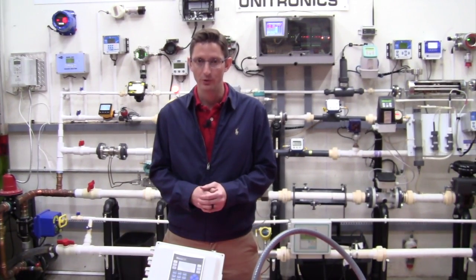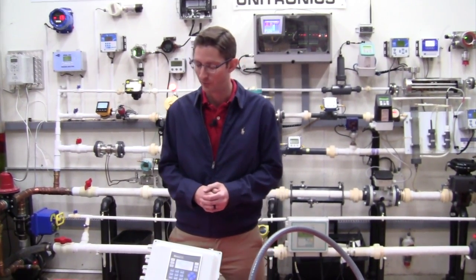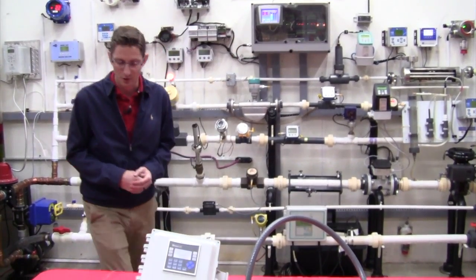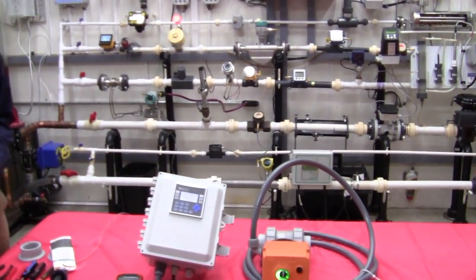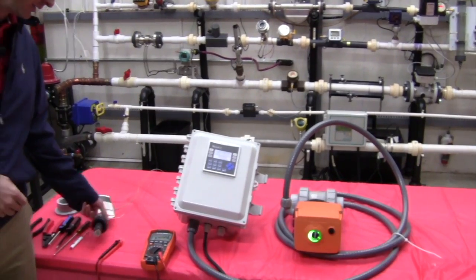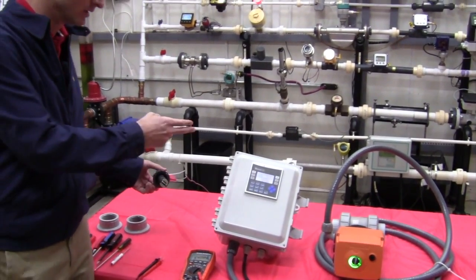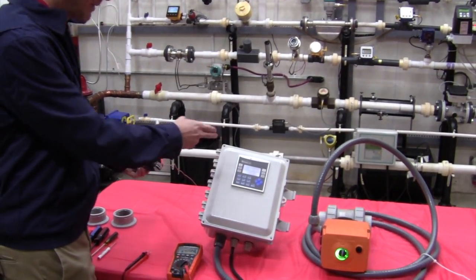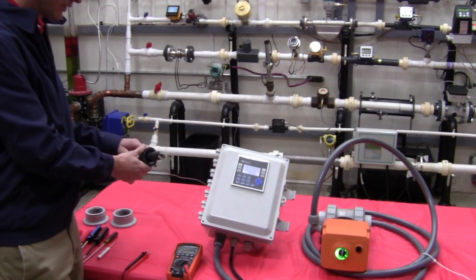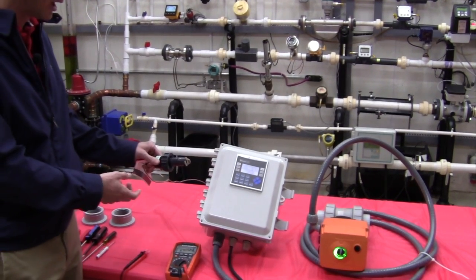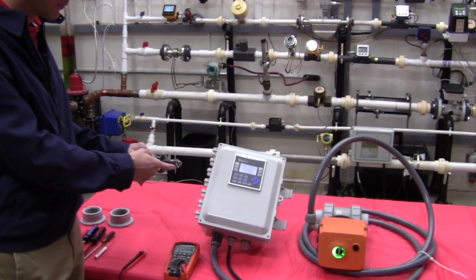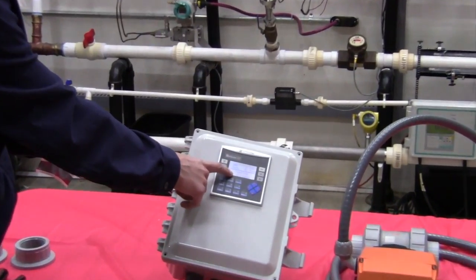Okay, now we're going to troubleshoot the flow meter system. I'm going to start by testing the paddle wheel. Excuse me, I should say I'm going to start by testing the pulses from the paddle wheel to the display. Right now I have my paddle wheel out of the line. If I give the paddle a spin with my finger, I should see it totalizing here.